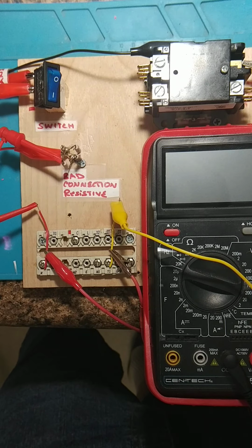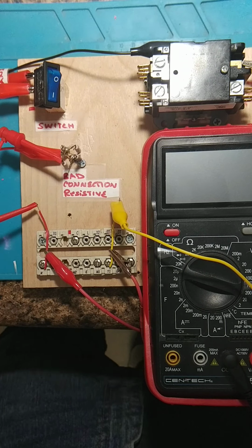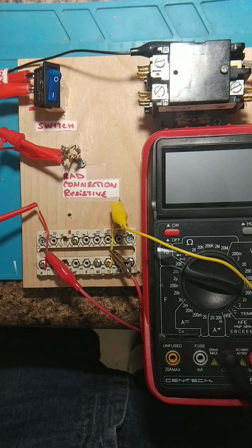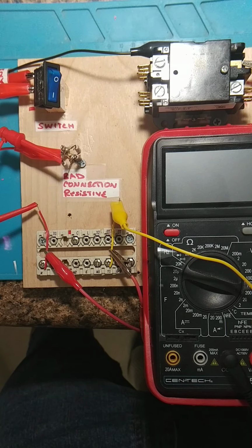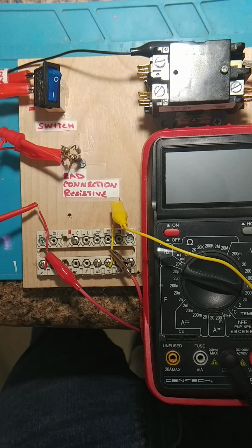Because a lot of times I've seen where, let's say you've got a straight cool condensing unit and you've got 8 conductor, whoever installed it, when they did a splice, they only spliced the 2 wires that are being used, a yellow and a blue. All the other wires, they're not even spliced. So you may have to go to those connections anyways and check those connections.